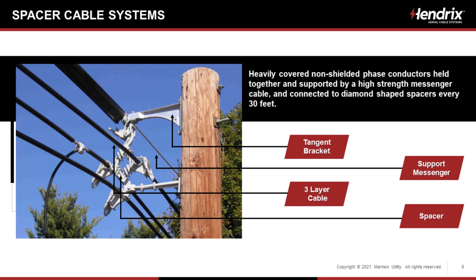You can see the spacer there. We've got one spacer every 30 feet, every 9 meters. And that's basically to hold the phase conductors on to the messenger. Those phase conductors have no tension in them. It might be 100, 200 pounds of tension. It's just like hanging a shirt up on a hanger in your closet. There's no tension on those phase conductors.